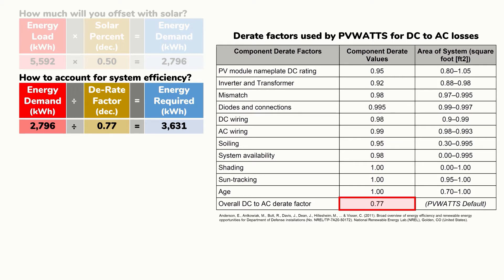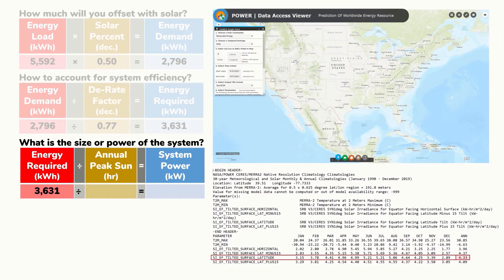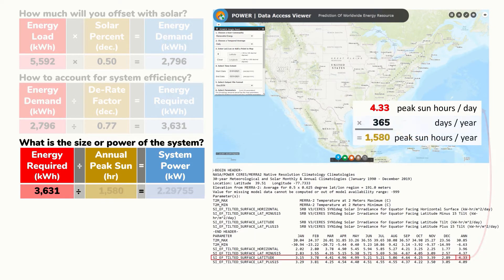It's also important to understand how much solar energy your site receives, since a solar panel converts solar energy into electricity. We'll use peak sun hours to express the amount of sunlight the solar panels will receive. In a previous video we saw how to evaluate peak sun hours from irradiation maps and resources including NREL's Solar Radiation Data Manual, NASA's Power Data Access Viewer, and the EPA's EnviroAtlas. For this example we'll use 4.33 kWh per square meter per day — the solar irradiance available at our research and education center in Kittsville, Maryland, assuming a tilt angle equal to our latitude of 39.5 degrees. Since peak solar radiation is defined as 1,000 watts per square meter, our site receives 4.33 hours per day of peak sun.